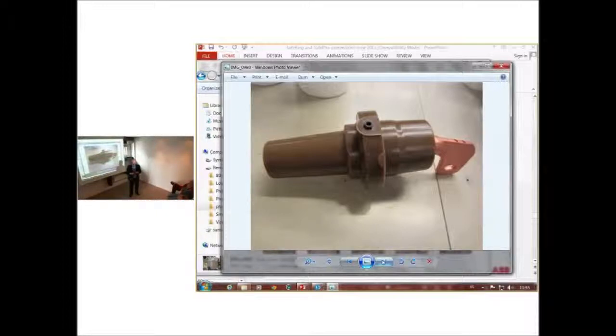There is a difference between VPIS versus VDS. ABB, we deliver VDS. They are both high ohmic, high resistance, but with the voltage presence indication system, if the voltage is on, this will have a red light. But then you need to question, if there is no red light, what is then the status of the voltage? In the former French specification, if there is no red light, you cannot know for sure. So in order to be 100% sure, you need the earth. That's what the norm says. With this one, VDS, you can be sure that it is high voltage.